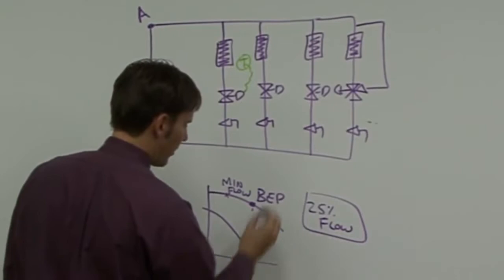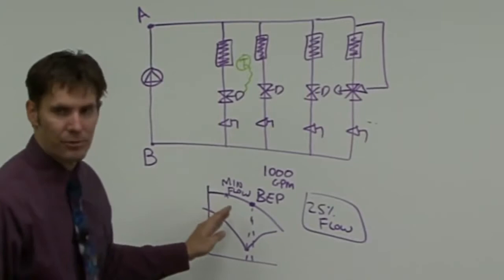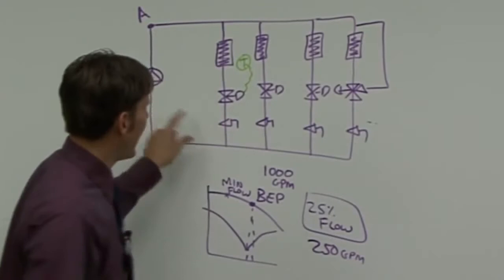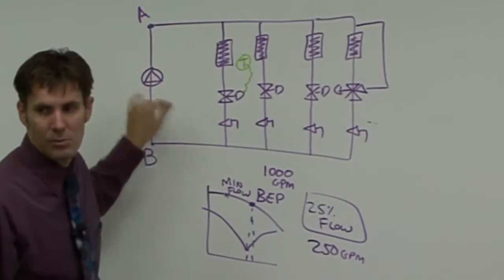If a manufacturer does not give you the minimum flow rate, the Patterson selection software does. A safe rule of thumb is about 25% of your best efficiency flow. So if your best efficiency flow is 1000 GPM and no minimum is specified, assume about 250 GPM. You'll need enough bypass so that you can keep that flow going and not damage your pump. When we apply a VFD to the pump, the rules start to change — as the VFD slows everything down, we don't have to satisfy this minimum flow requirement in the same way, and we'll talk about that later.